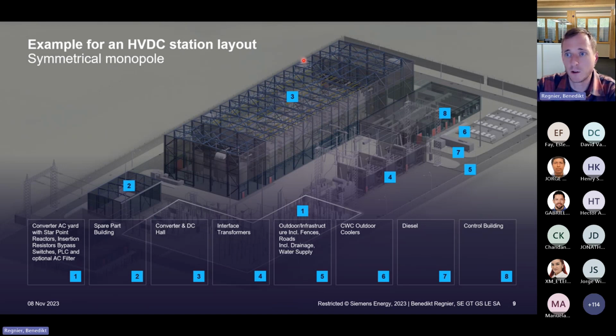Number 3, the heart and soul, of course, the converter hall. In this case, we also have the DC halls, two here and here, as an indoor solution. This could also be outdoor. Again, it depends really strongly on the project, on the environment that we have there, on the limits which are given for EMC. And then we can decide if it's indoor or outdoor. Interface transformers serve as coupling to the grid, limiting of fault currents, and also adapting the AC voltage which is needed for producing the DC voltage.